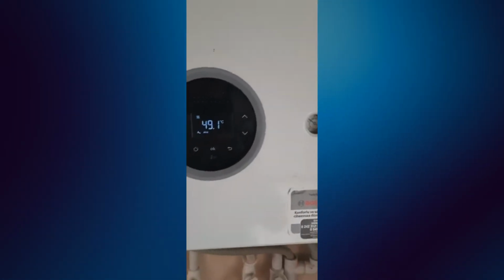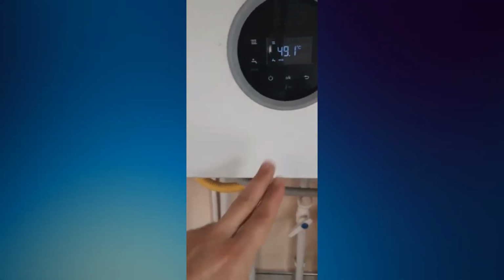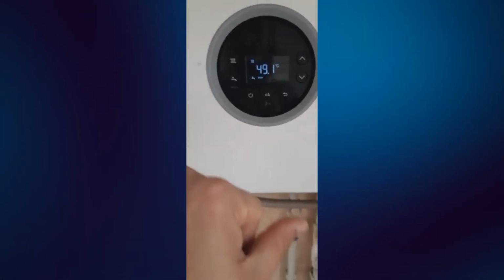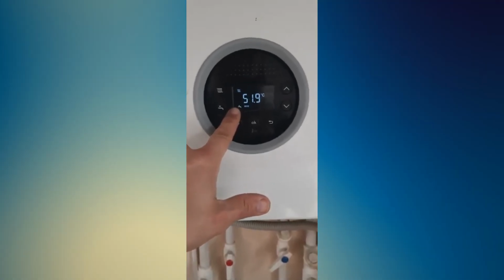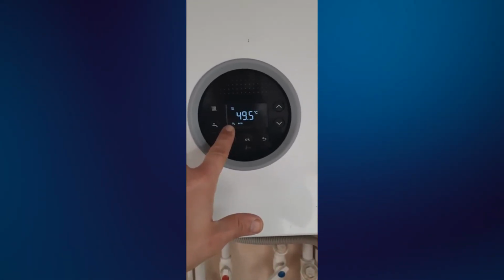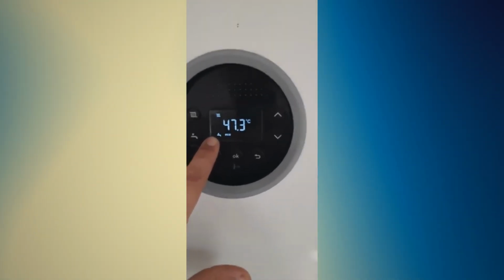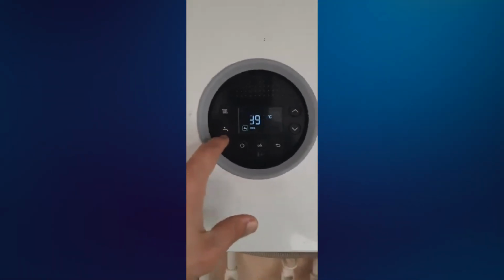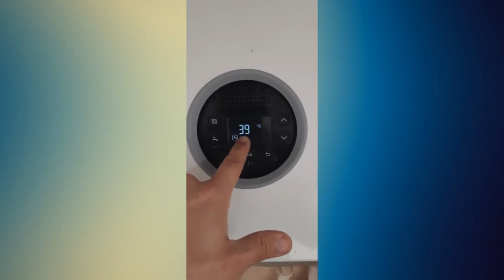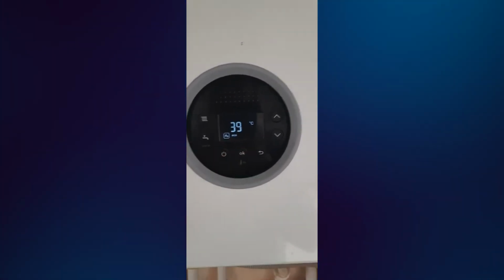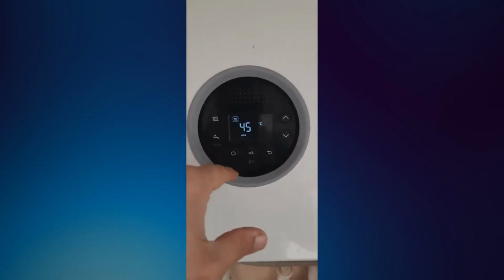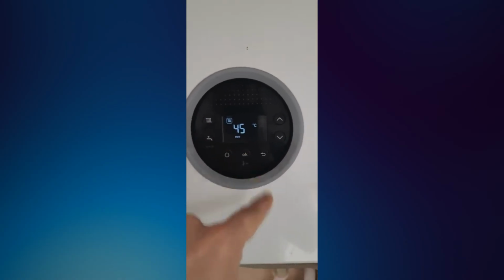If error 2951 appears once and clears after correcting low pressure or thawing a frozen condensate pipe, monitor the boiler carefully. If it appears again, call Bosch, Buderus, Worcester support, or a qualified heating engineer. When you call, provide the exact model number, the full error code, and the symptoms. Also mention whether the pressure was low, whether hot water works, whether central heating works, whether the condensate pipe was blocked or frozen, and whether the boiler tries to ignite before locking out.